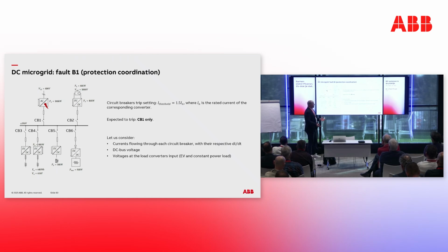And the argument was, well, you know, I stopped switching, right? So from the AC grid, I have no contribution. The only contribution to the short circuit is going to be the capacitor, and I'm fine with it discharging because the loads, the critical loads, can ride through the voltage zero for several milliseconds and then come back online once we clear the fault and open an electromechanical switch. And at first I was like, okay, that's actually a fair argument.